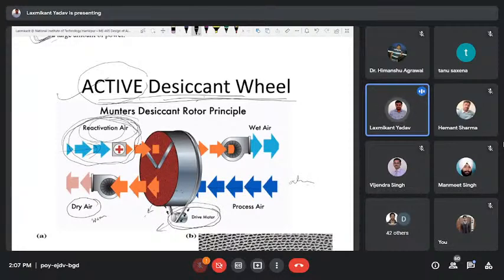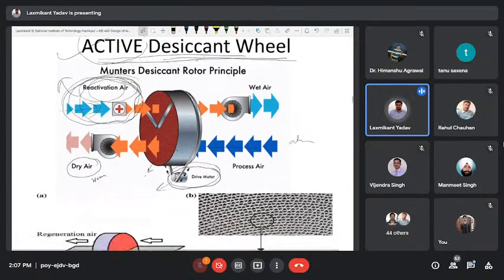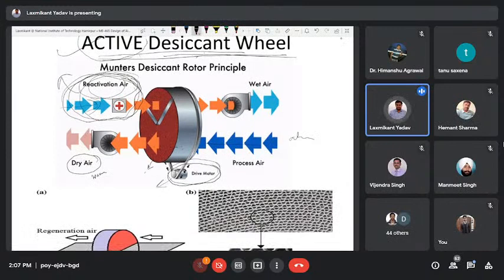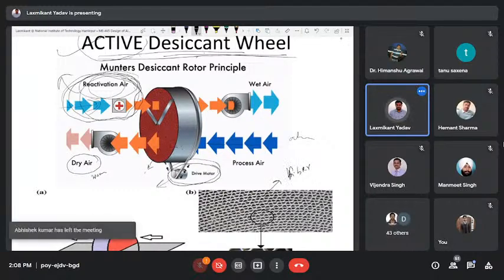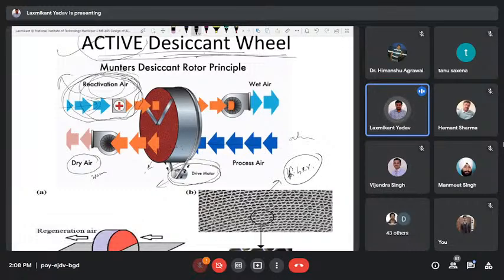So the advantage is that it can be operated at a low regeneration temperature, 60 to 80 degrees Celsius, and that temperature we can easily achieve by the solar air heater or waste heat, okay, of the industry. So this is the cross section of the desiccant wheel. You can see the cross section is like a sinusoidal channel. First we make a sinusoidal channel of fiber. On that fiber, we deposit the silica gel desiccant or molecular sieve desiccant. That fiber is initially called the matrix material or substrate. Okay, and on that substrate we coat the desiccant material.